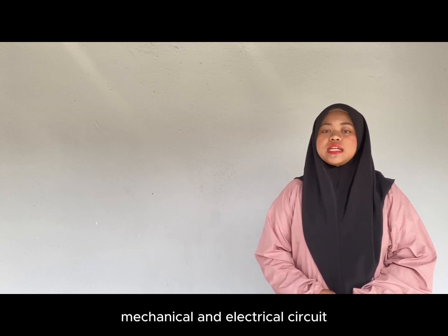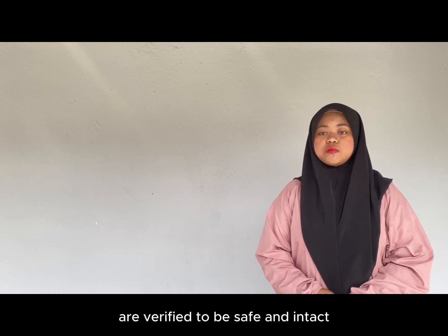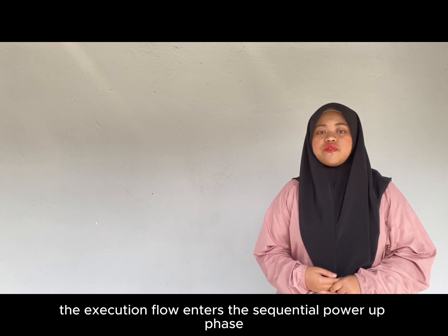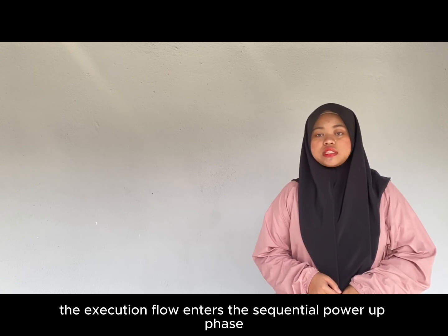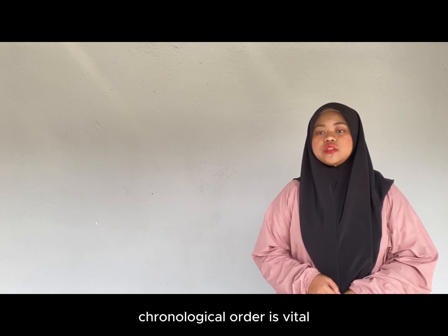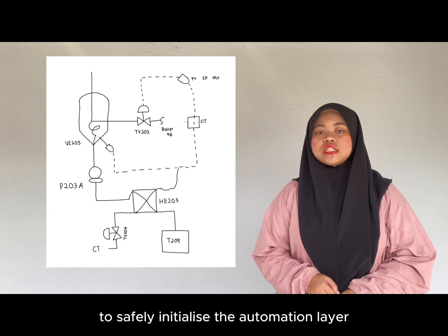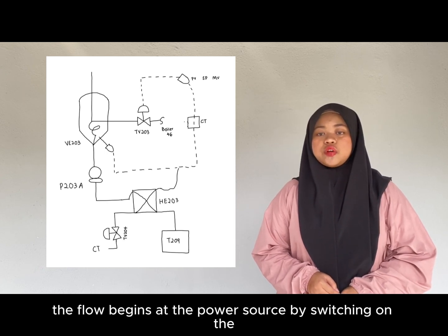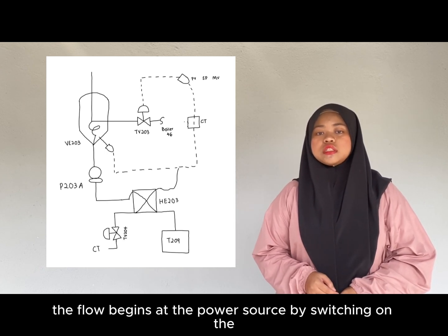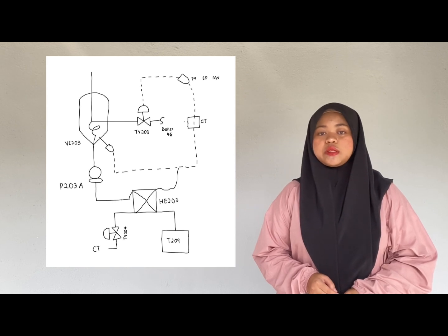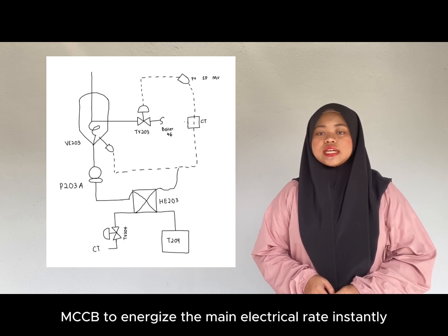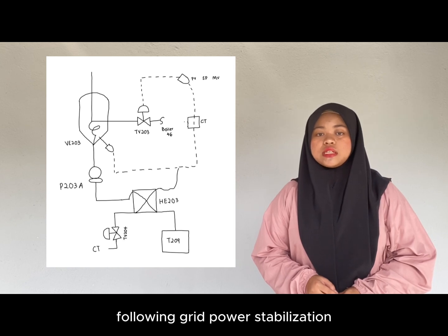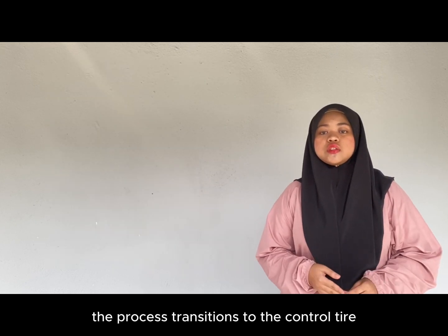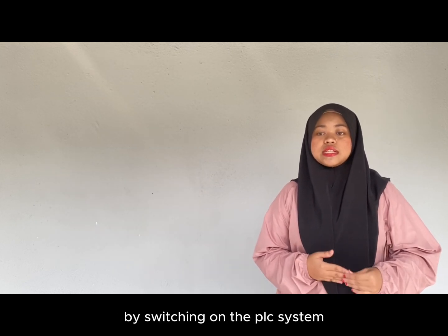Once the physical, mechanical and electrical circuits are verified to be safe and intact, the execution flow enters the sequential power-up phase. In this phase, maintaining a strict chronological order is vital to safely initialize the automation layer. The flow begins at the power source by switching on the molded case circuit breaker, MCCB, to energize the main electrical grid. Instantly following grid power stabilization, the process transitions to the control tier by switching on the PLC system.